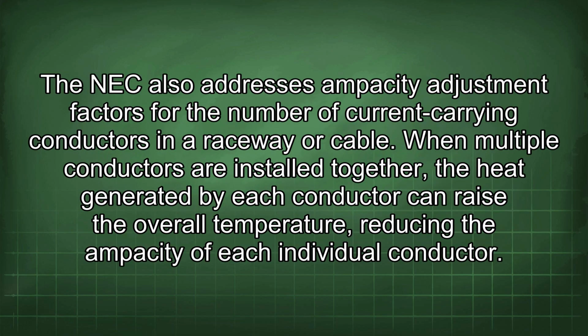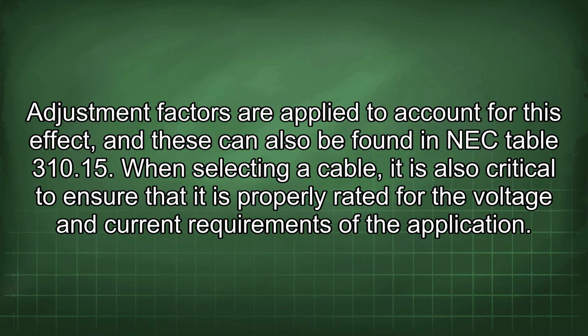The NEC also addresses ampacity adjustment factors for the number of current carrying conductors in a raceway or cable. When multiple conductors are installed together, the heat generated by each conductor can raise the overall temperature, reducing the ampacity of each individual conductor. Adjustment factors are applied to account for this effect, and these can also be found in NEC Table 310.15.